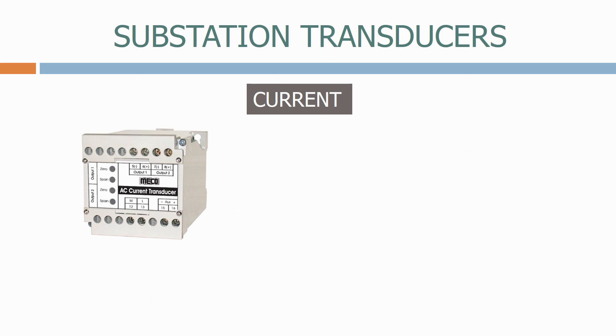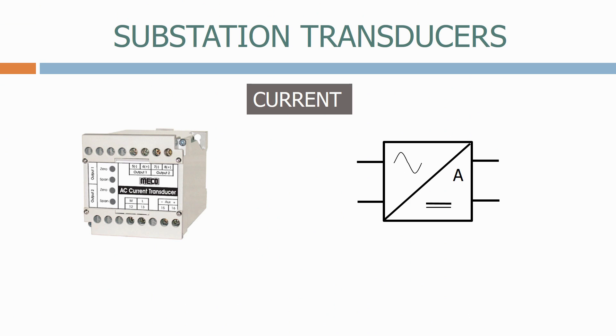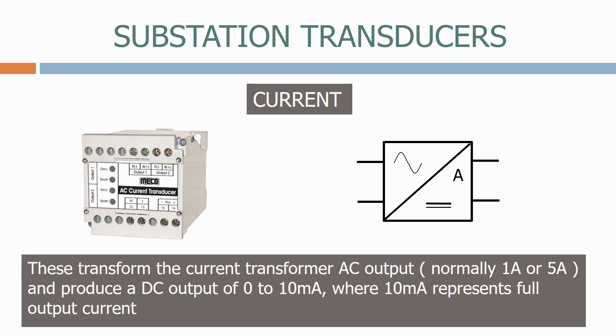Next, we have a current transducer. This is the symbol we normally use. These transform the current transformer AC output, normally 1A or 5A, and produce a DC output of 0-10mA, where 10mA represents full output current.